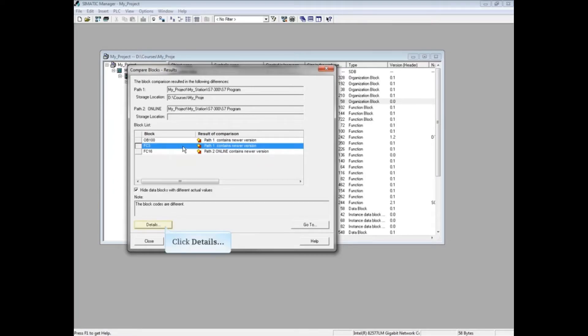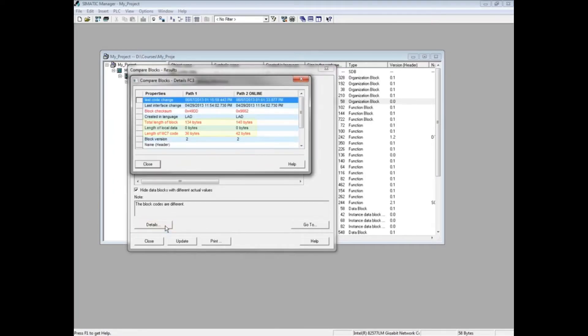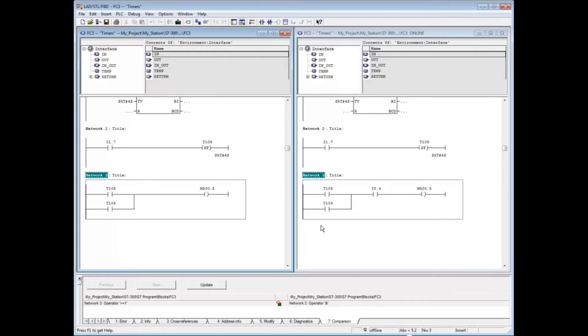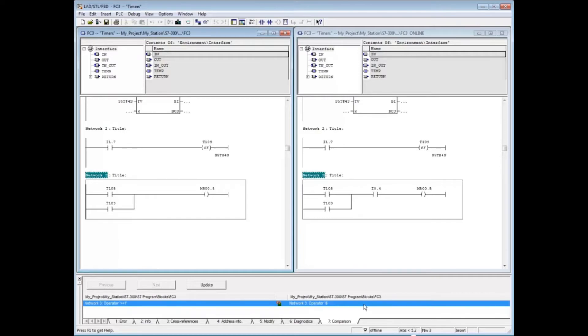In the comparison list, FC 3 is also newer in the offline version. Highlight FC 3 and click the Details button if you want to see a description of the changes. Here you can see that the offline block size is smaller than the online block size. Close the details window and click the Go To button.